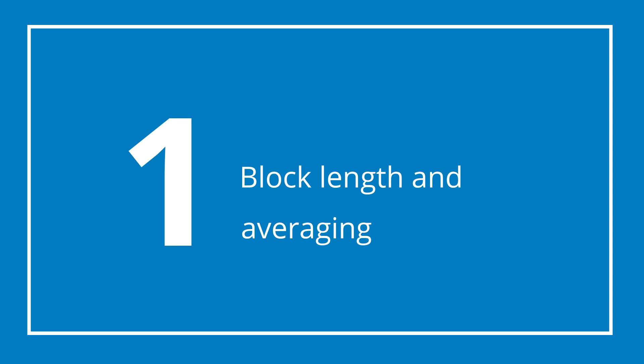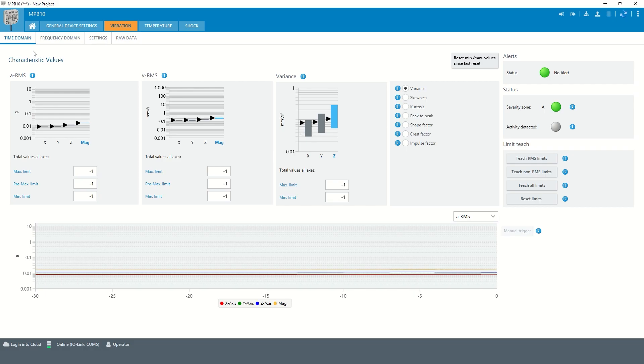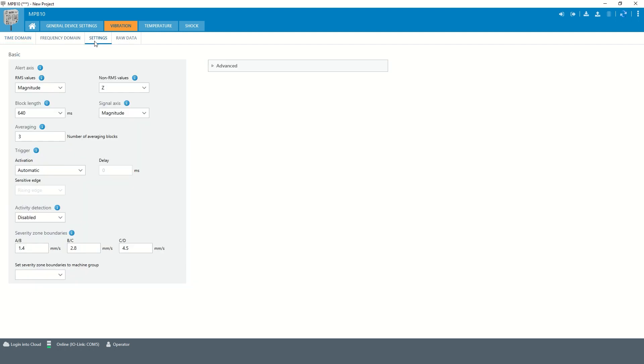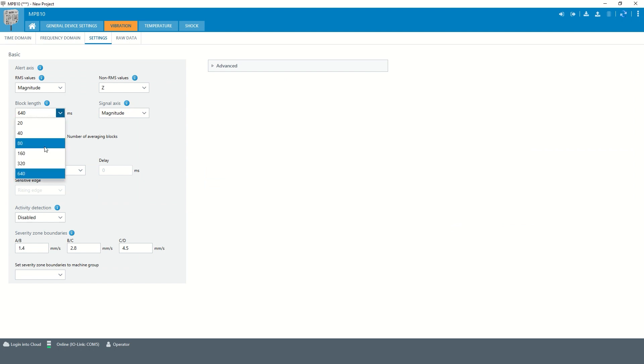Chapter 1: Block length and averaging. The time domain key values are calculated based on a block of recorded vibration data. The length of this block can be adjusted in the settings. The block length can be set between 20 milliseconds and 640 milliseconds. In single axis mode the block length can be even extended to 1280 milliseconds.